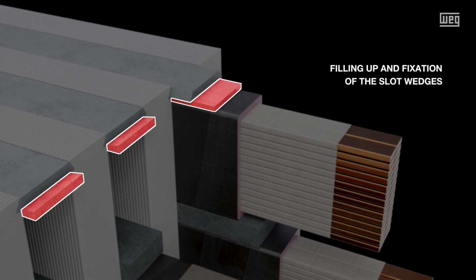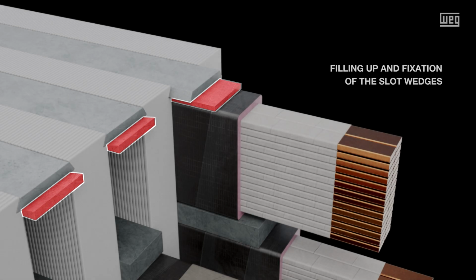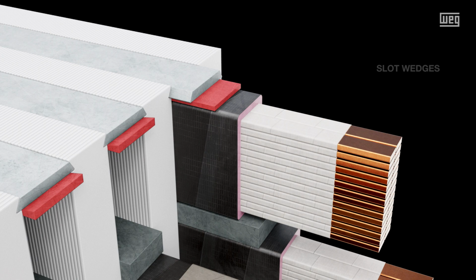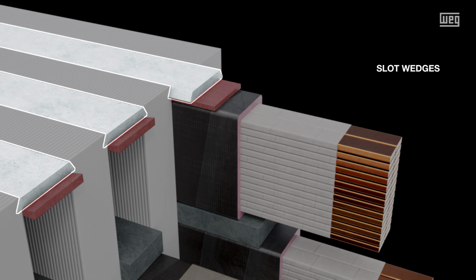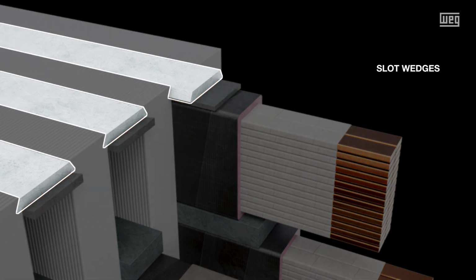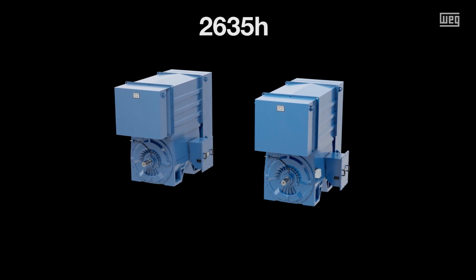A swellable laminate is placed under the slot wedges. After the impregnation and curing processes, it becomes a solid composite, preventing the wedges from vibrating in service. Magnetic and non-magnetic slot wedges are used to hold coils in place during the production. In operation, the wedges can reduce the air turbulence in the air gap of the machine, in addition to contributing to its overall electromagnetic performance.